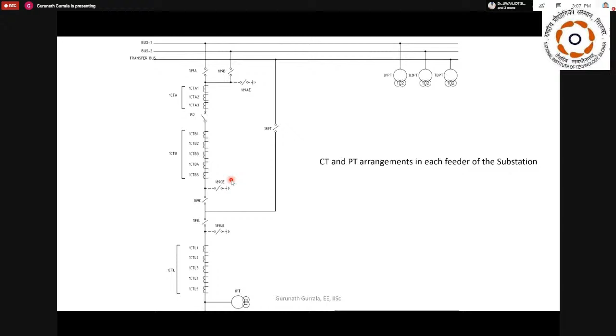And we also have a potential transformer, which is both metering and protection class, with two secondaries. Again, for each bus, you have the protection PTs. And this is how a real substation will be implemented. It's not a single CT or a single PT. There will be multiple PTs and multiple CTs coming in. That is why protection in the field is actually challenging.